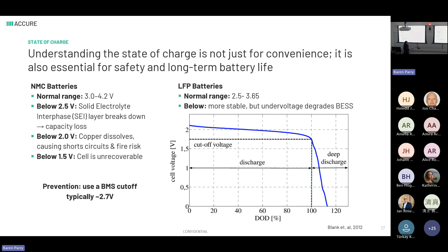For LFP batteries, they are a little bit more stable. You can still have a lot of risks of degrading the BESS with any undervoltage or deep discharge, so typically there is a BMS cutoff set around 2.7. But the main point is that you really cannot go into deep discharge without risking the safety of your battery as well as the life of your battery. So the problem is that's not an easy equation.